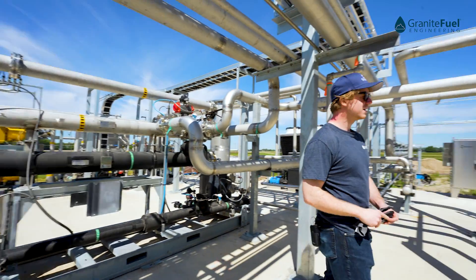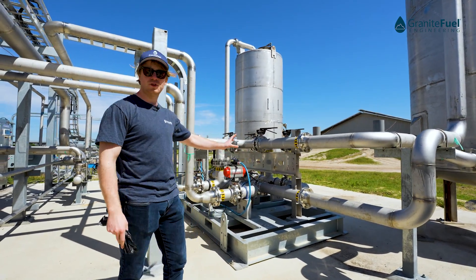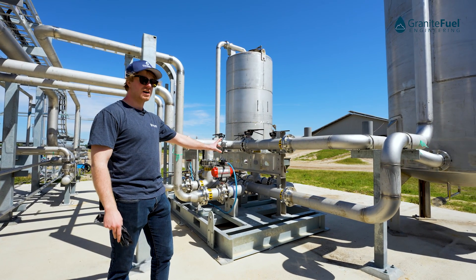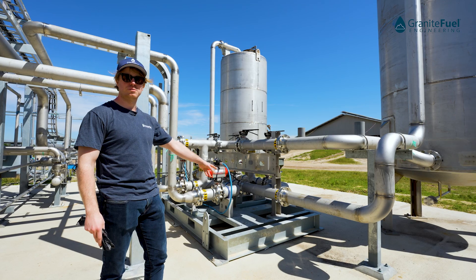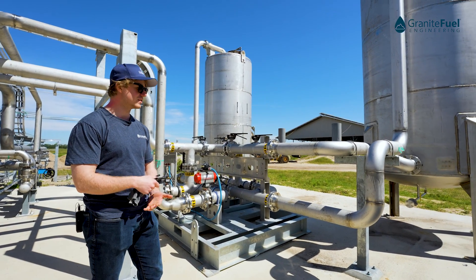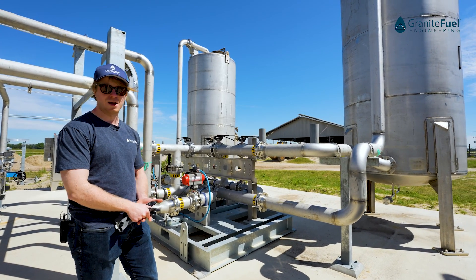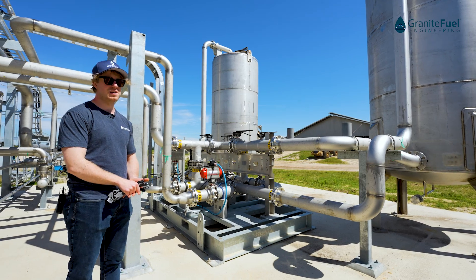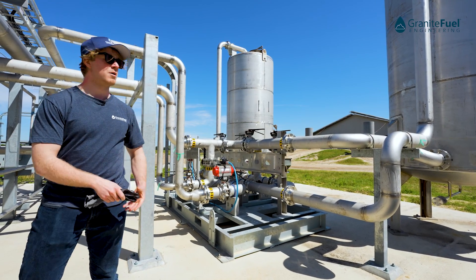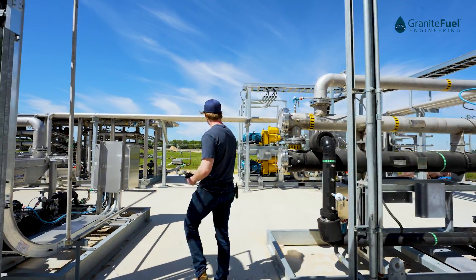The next step in the process, it gets sent over to our activated carbon polishing system. We have two vessels with static media and a lead-lag valve skid. This step is to remove any latent VOCs you might have in your biogas, any siloxanes, or anything else that might impact the downstream upgrading process. Once we're satisfied that the gas is clean and ready to be upgraded, it's going to come over to our Granite Fuel compression system.